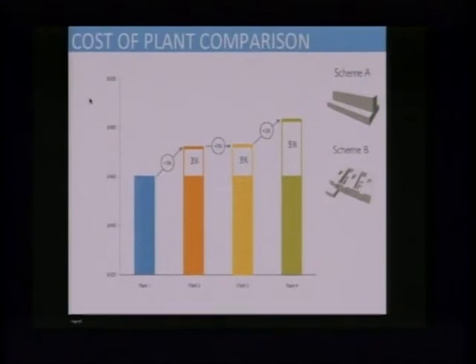Looking between the high performance models, it's pretty similar between Scheme A and Scheme B, so I'm just going to show one number. It ends up being about the same. To shift from a high performance model to plant 2 and 3, it's about a 3% cost add. For plant 4, which includes the bore field, it's about 5%. This number came from when we sized the bore field to the peak, so we're hoping this number is going to go down a little bit - we're not sure yet.